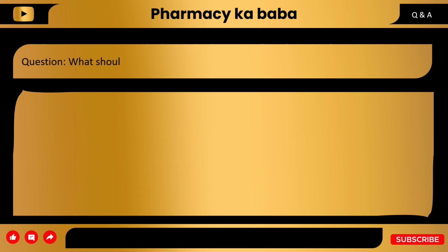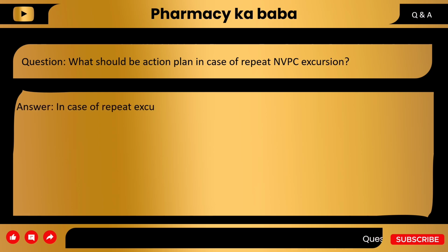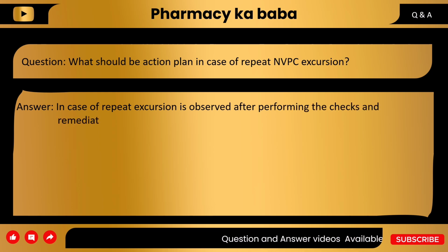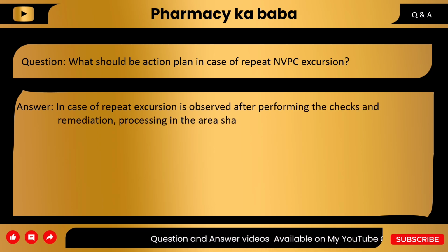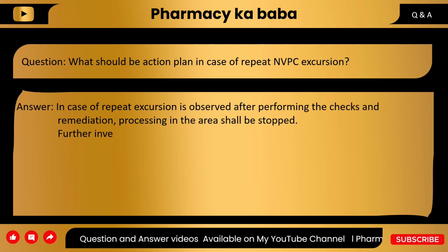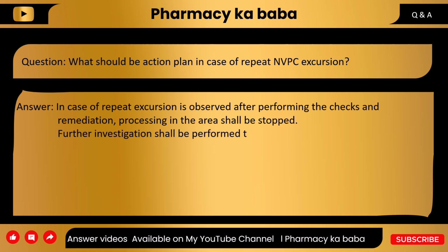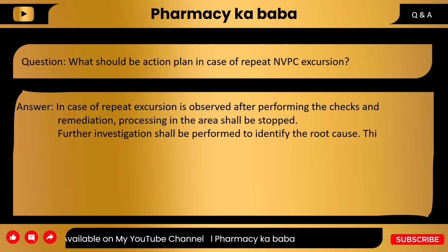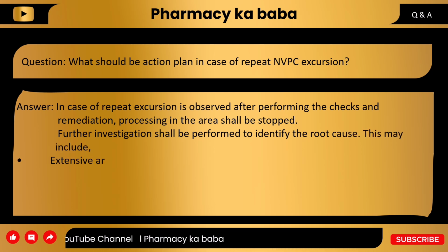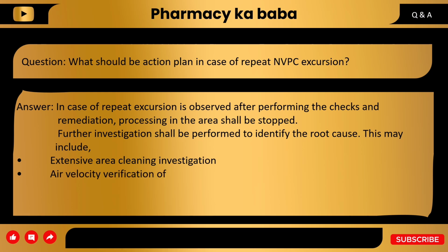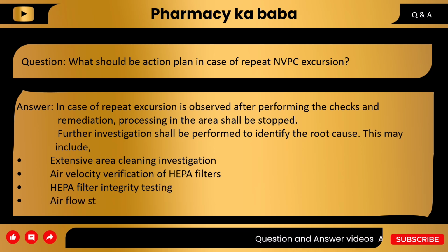Question: What should be the action plan in case of repeated NVPC excursions? Answer: In case of repeated excursions, after performing the check, the process in the area shall be stopped. Further investigation shall be performed to identify the root cause. This may include extensive area cleaning investigation, air velocity verification, HEPA filter integrity testing, and airflow studies.